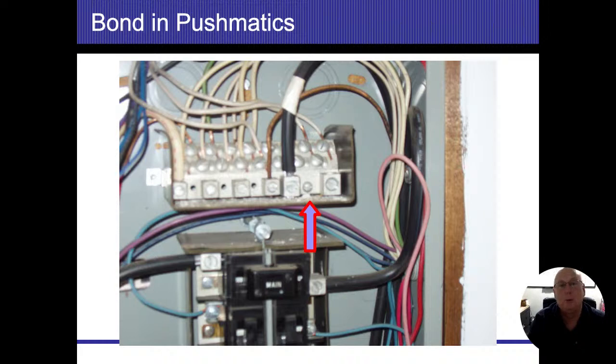In this case, on the Pushmatics, that little screw there to the right of the GEC, that's going to be my bond screw that comes in there.